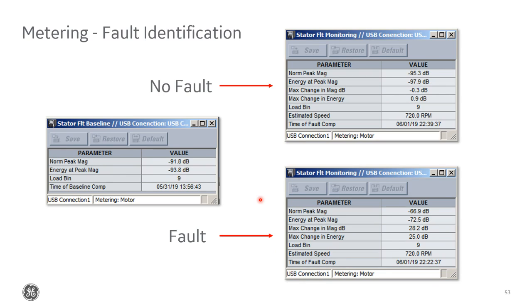So what if a fault happens? What would you see? Here we're looking at the values for the stator category. On the left again is the recorded baseline values. And on the right, we have the monitoring screen, which I've condensed a little bit for clarity. If there's no fault, everything's normal, you can see both the normalized and energy peak magnitudes are fairly close to negative 100, which remember is a good thing. This means that there's barely any signal there compared to the fundamental. And these values compared to the baseline values are pretty close. You can see the max change value is pretty close to zero, so no issue here.